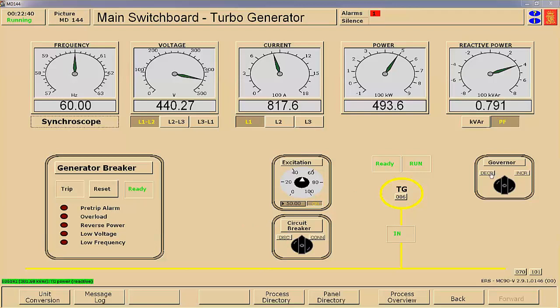On my second screen, I have diesel generator number 2 up. And to take it off the line, I am going to decrease the governor on the turbo and increase it on the number 2, and you keep doing that in short. Be very careful. You have to double click. It stays in if you're not careful. So you click it in and then out. So you click and click, double click, and you keep transferring back and forth.